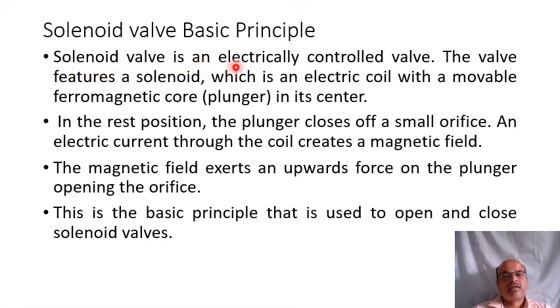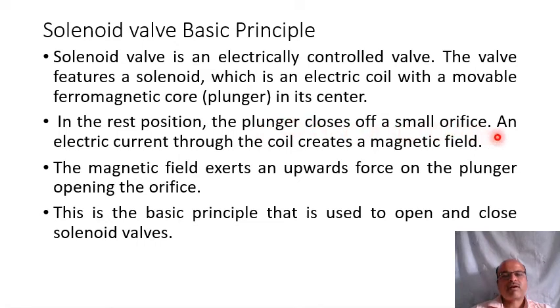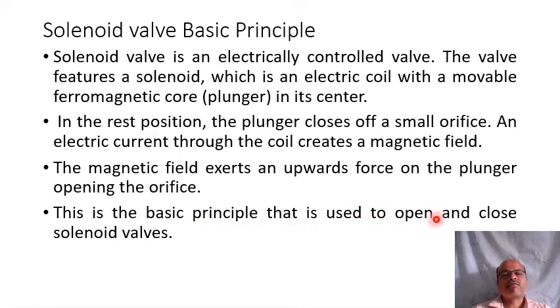The basic principle of a solenoid valve: it is an electrically controlled valve featuring a solenoid, which is an electric coil with a movable ferromagnetic core called a plunger in its center. In the rest position, the plunger closes a small orifice. Electric current through the coil creates a magnetic field, which exerts an upward force on the plunger, opening the orifice.